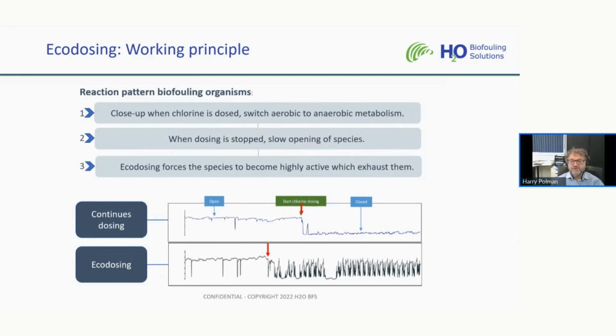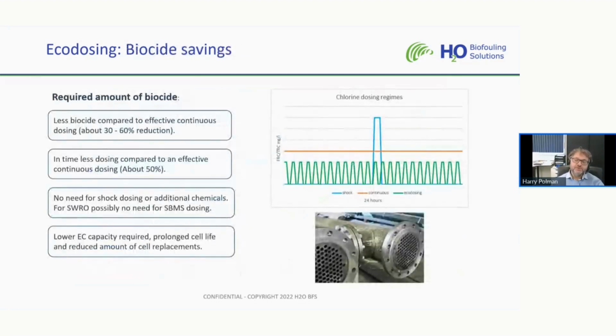This behavior uses a lot of energy, and in practice these animals exhaust themselves. So instead of trying to kill the animal with a biocide, you use the biocide as a trigger to stimulate the organisms to become highly active so they exhaust themselves. In practice, you need a lower concentration than continuous dosing to be effective, since you don't need to kill them, only trigger activity. You also don't need shock dosing, because a high concentration doesn't impact the animals — they simply protect themselves by closing their shells.